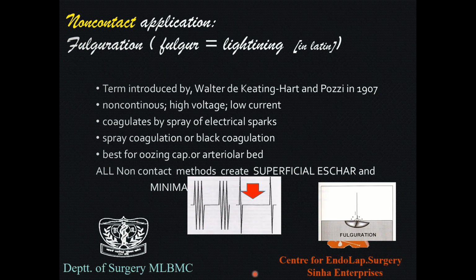Now, the non-contact application, the second is what we know as fulguration. That fulguration, lightning, I told you, was a term introduced by Keating-Hart and Pozzi in 1907. Here, what we're talking about is non-continuous. This is not continuous, so non-continuous, high voltage and low current. Why? Current is here only for this time and this time. So low amperage, high voltage, non-continuous current. And how does it coagulate? It coagulates by a spray of electrical spark.